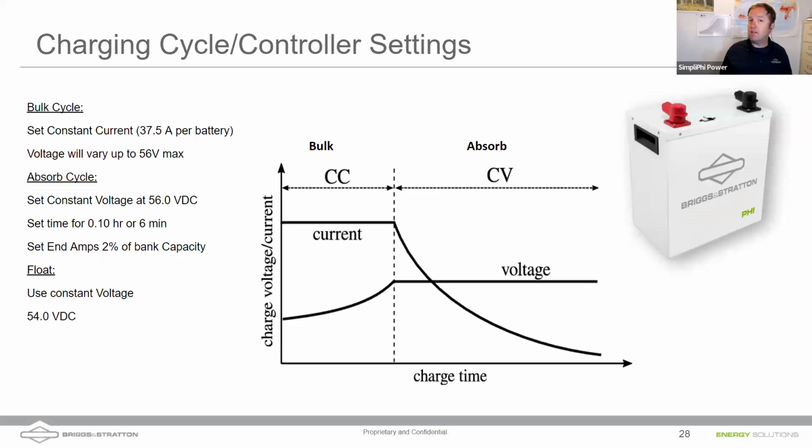A lot of times we don't want to float the batteries with a generator, because there's no real need to. We'd rather go through those cycles. We usually don't float the batteries with grid either. What we do want to do is float batteries from solar. If we have, for example, an off-grid system and the solar is kicking in and providing enough power for the loads, we're going to just keep those batteries floating. In grid-tied situations, it's a little more dynamic. A lot of times we can tell the inverter what priority we want that energy to go to, whether we want to send it back to grid, support loads first, or charge the batteries first. As it used to be, just get a charge controller and charge a battery. But now with these more dynamic systems, we can really tell the system where we want energy to go first and in what priority.